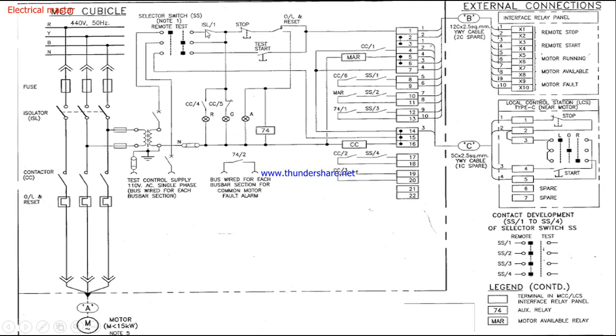So when the selector switch is closed, the power supply is further connected to the stop pushbutton at the local MCC panel. The stop pushbutton is a normally closed (NC) contact. Then this power supply connects to the NC contact of the overload relay. Until the overload relay receives any fault or overload current, this relay remains normally closed. Further, it goes to the terminal block.